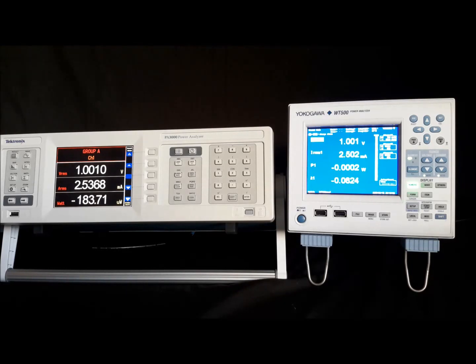Okay, so how low can the Yokogawa go? It's 2 milliamps, 1 milliamp, 500 microamps, 400 microamps. Bit of a deviation in coming on there. 300 microamps. Okay, cuts off there, so 300 microamps. Again, a good range, considering that it's on the auto range for the current input. It's on an auto range on current input for the Tek as well. Yeah, quite a significant difference, as you can see there, on the voltage ranges and on the current ranges as well.